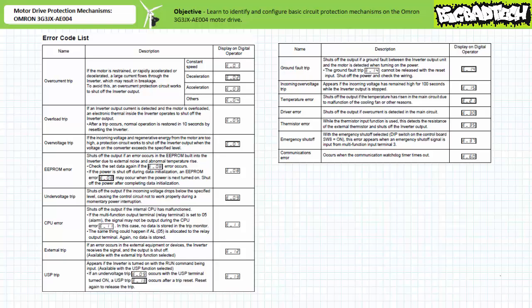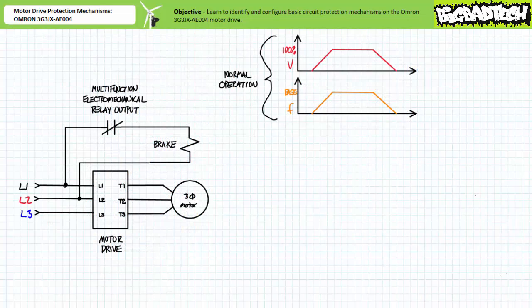For our purposes, we'll assume the drive's response to any of these fault conditions is to signal an alarm and output the appropriate error code. Should a fault occur, the drive will log the time and value at the time of occurrence and execute the preprogrammed response. Beyond the passive recognition of a fault, the OMRON 3G3JX AE004 motor drive can be configured to actively respond to an error using the multifunction digital output P1 or the multifunction electromechanical relay output executing the 05 alarm output function.